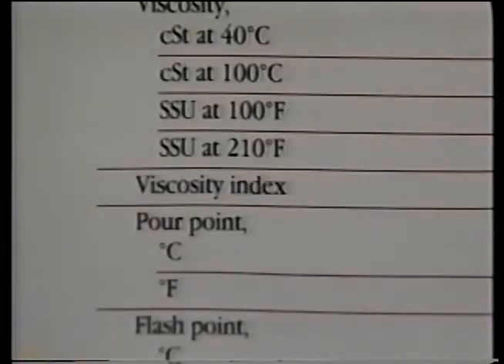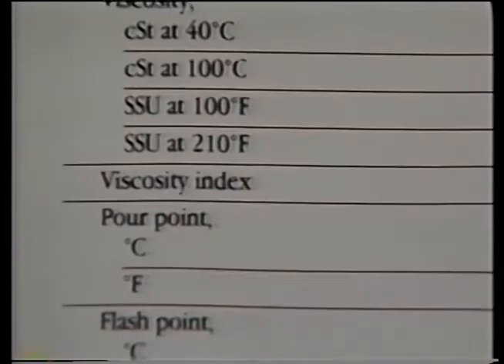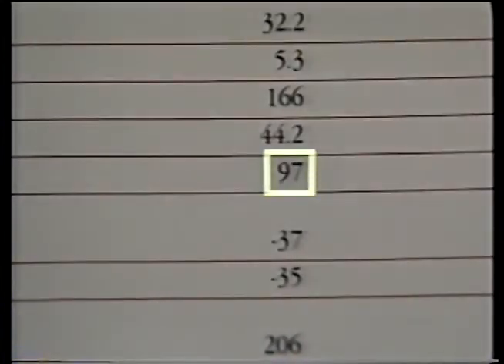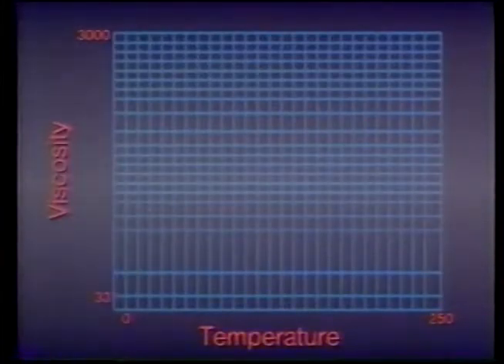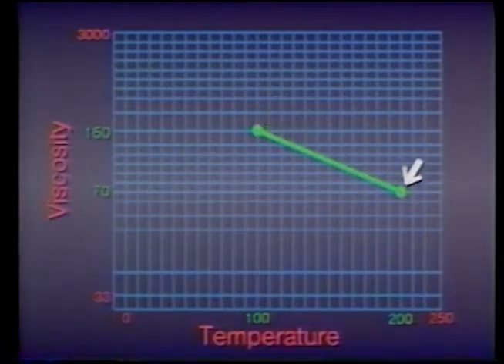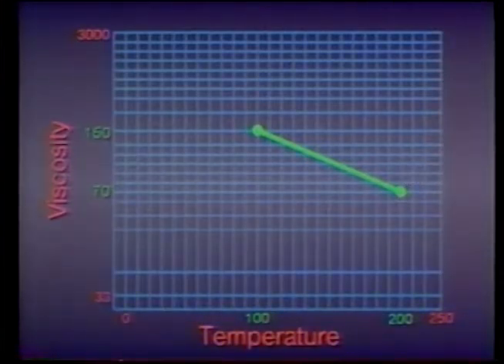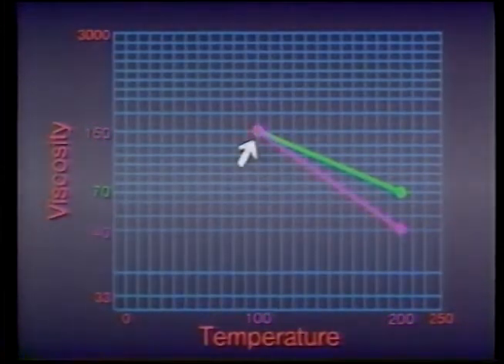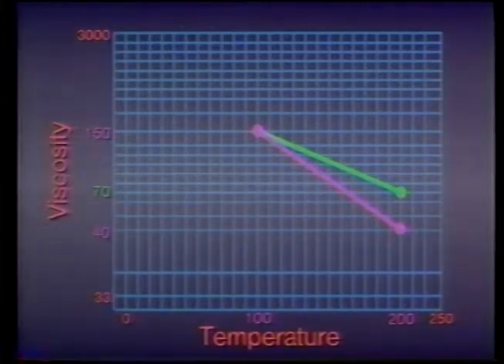The change in a fluid's viscosity at different temperatures is referred to as its viscosity index. The higher a fluid's viscosity index, the less the fluid's thickness is affected by temperature changes. For example, the viscosity of a fluid with a high index may change from 150 SUS to 70 SUS as the temperature rises from 100 to 200 degrees Fahrenheit. But the viscosity of a fluid with a lower index might change from 150 SUS to just 40 SUS over the same temperature range.